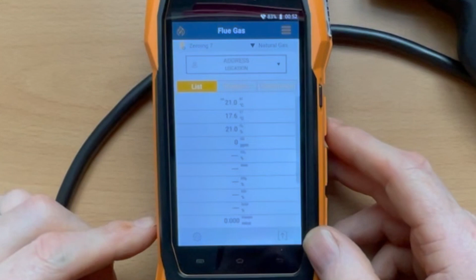This analyzer takes a little while to turn on initially, and then it takes 30 seconds to do its purge for the flue gas analyzer. But it does have a quick off and on function. If you press the button once, it turns itself off. Press it again, it turns itself on instantly and doesn't go through the purge sequence. Also, depending on what setting you've set it to, it will shut down automatically on its own but won't turn off, it just puts the date and stuff on the front screen, and then you just press the screen and it rings back up again, you don't even need to press a button. That's a nifty little idea they've got after the initial turn on, so you could actually leave it like that all day without turning it off. Quite a good idea.